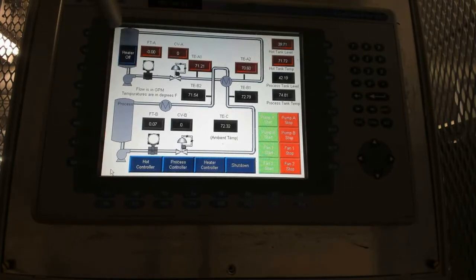So in this system, in this loop here, we're constantly adding heat, and then we're transferring that thermal energy from the heat transfer fluid into the process fluid. And those two fluids never touch. They're not combined. They're going through what's called a plate heat exchanger.